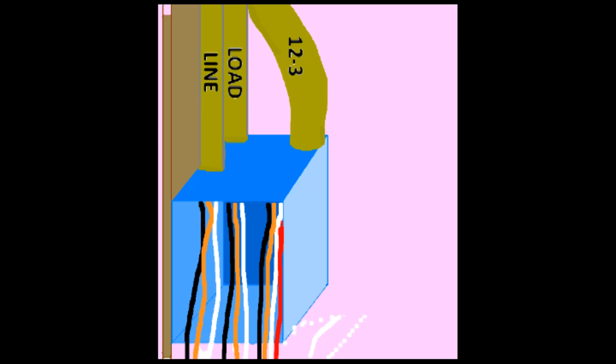You see that the main box has one 12-3 and two 12-2s running into it. One of the 12-2s is the feed or line and the other 12-2 is the light leg or load.